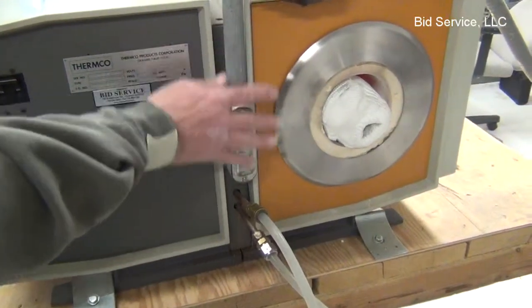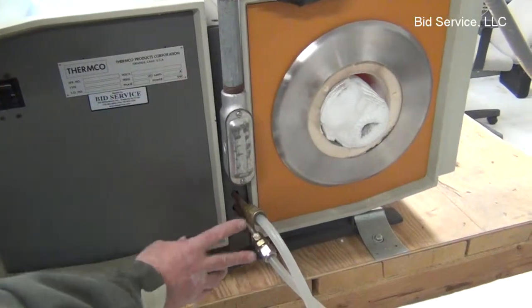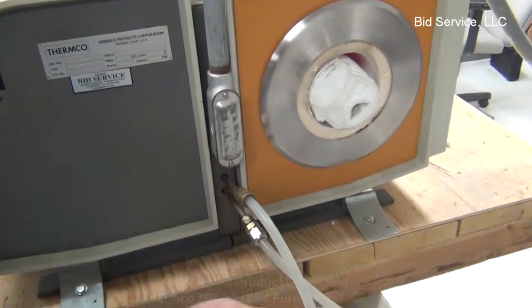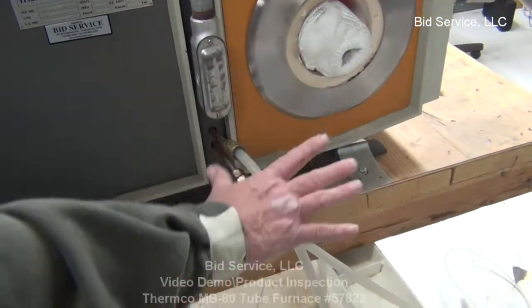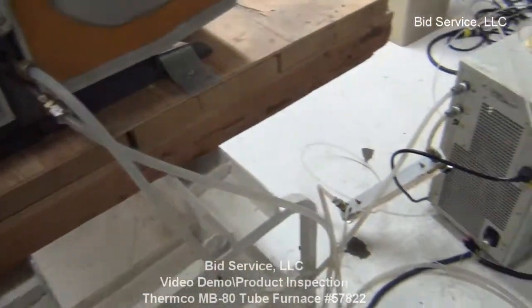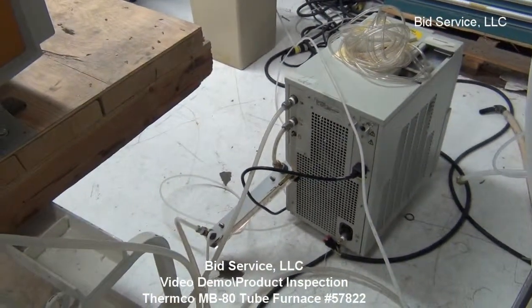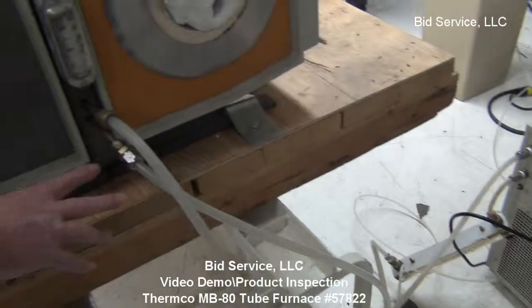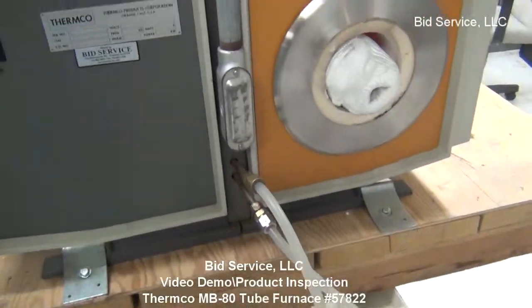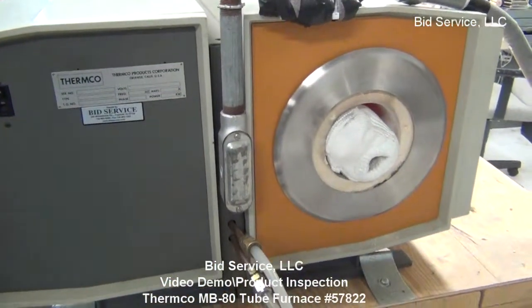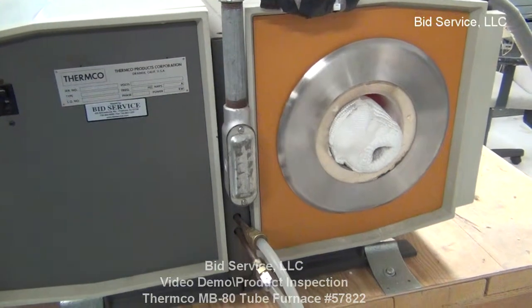On the back here, you can see our power connections are here, and down here are the water cooling. I have this hooked up to a chiller, which is not included, but if you're going over 600 degrees, you need to have cooling water plumbed into this unit to maintain temperature properly and not overheat.